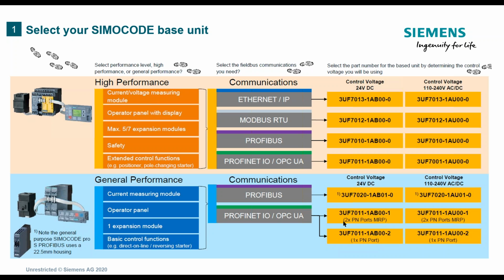And then if you were not going to communicate, just going to go from the SIMOCODE directly to the PLC with no star topology or anything like that, then I would go with the 1-port version to where it only has 1 Ethernet port. And then if you did 120 volt control, then I would use that 1 expansion module for the 120 volt digital input card. So there'd be 4 part numbers that I would quote you. This guy here, the expansion card, the cable, and then the PT-CT, or sorry, just the current transducer for it.